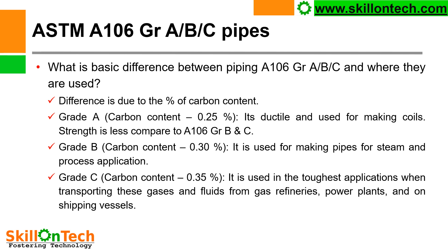Grade C pipeline — ASTM A106 grade C has carbon content of 0.35%. It is used in the toughest applications when transporting gases and fluids from gas refineries, power plants, and on shipping vessels. The strength of grade A is less compared to grade B, and grade B strength is less compared to grade C. But ductility is reversed.